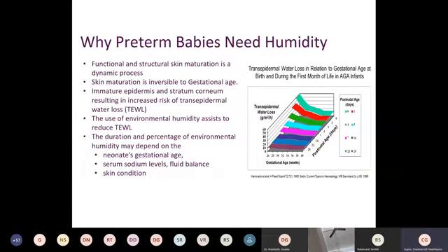The next one is the humidity. Whenever we talk about an incubator, we need to understand that these are very, very fragile babies, and this chart shows that the more premature the baby is, in the initial days of the gestational age, during this time the fluid loss is the maximum. Because if you really notice, for the first few days the babies lose weight, and because they lose lots of fluid, it's a challenge for the IV fluid management.